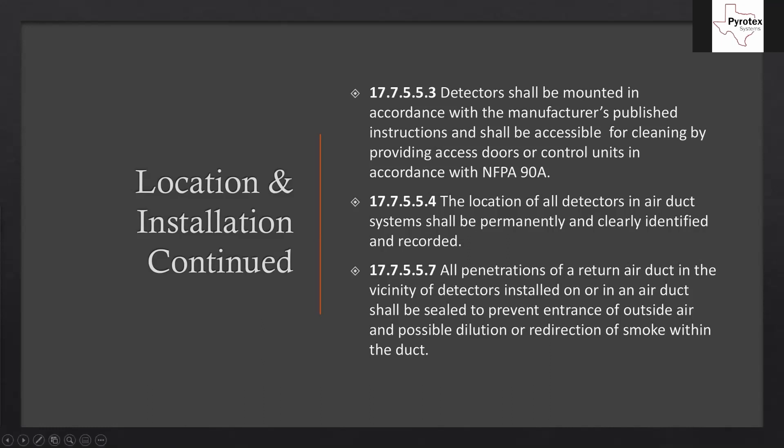The last point: all penetrations of a return air duct in the vicinity of detectors installed on or in an air duct shall be sealed to prevent entrance of outside air and possible dilution or redirection of smoke within the duct. Where the duct detector housing meets the duct, we need to seal it — aluminum duct tape works well. The venturi vacuum effect can be compromised if it's not sealed properly, allowing smoke to leak around the housing instead of passing through the detector.